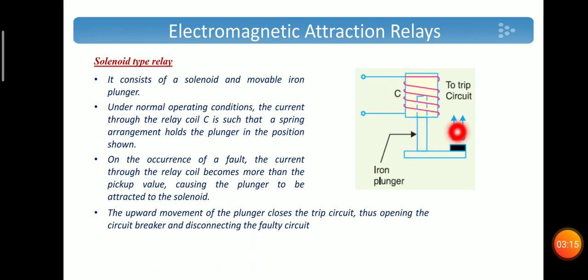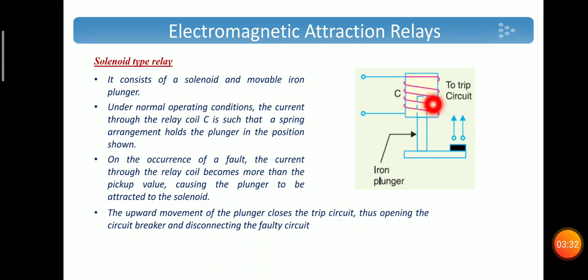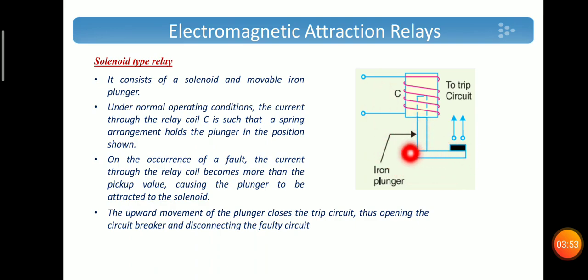The only difference is in the construction. It consists of a solenoid and a moving iron plunger, and the solenoid is wound with a coil which carries the current in the system to be protected. Under normal condition there is no attractive force. When a fault occurs, the attractive force increases, the iron plunger is attracted towards the solenoid, and the trip circuit gets closed. The iron plunger is held in position under normal condition by a spring arrangement; when a fault occurs, the force exceeds the spring force and the trip circuit closes, operating the circuit breaker.